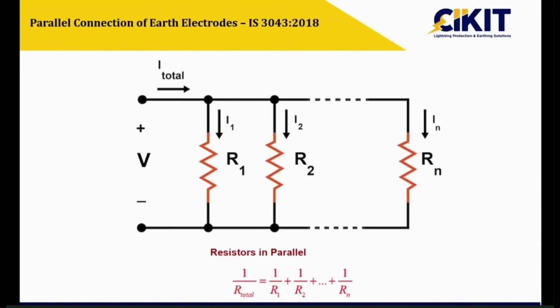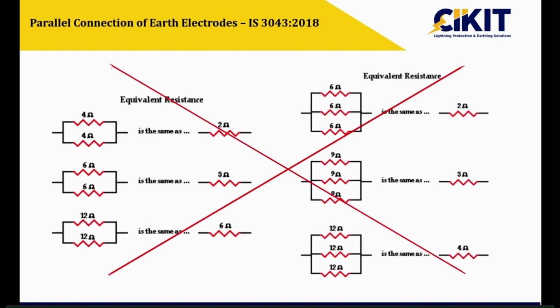If you take this parallel connection, which is commonly used by many people, many people are using the particular formula which we use for calculating the resistance value of multiple resistors. If we have two resistors in parallel, the combined resistance will be R by 2. If we have three resistors in parallel, the combined resistance will be R by 3. This is the formula many people commonly use for earthing also. But this is not at all applicable to earthing, because the formula we are seeing here is for ohmic resistance. It does not depend upon the surrounding environment, but the resistance we deal with in earthing is in an electrolytic environment, which mainly depends upon the surrounding environment. So the formula used for electronic circuits is not at all applicable to earthing.